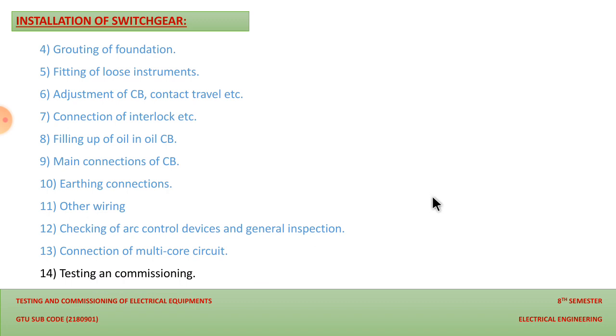So after installing our switchgear at the premises, we should perform certain tests related to the operation of the circuit breaker, and we should also perform a commissioning test for the proper operation of our switchgear when we are connecting it with the main system. So these are the points that we should follow while installing a switchgear.